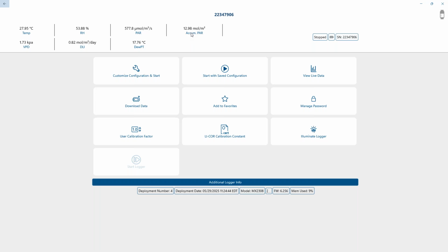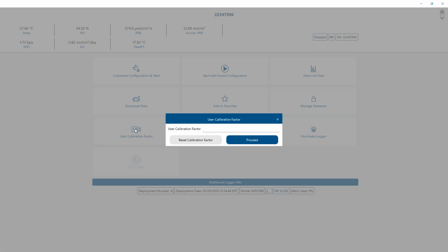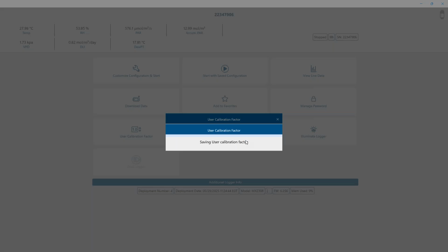I have this one logging every minute. You can see it just updated a second ago. So this will update at the logging interval. The user calibration factor that I touched on, let's imagine you 2 years down the line and you want to use this product. For the user calibration factor, this is where by default is 1.1. If you wanted to change it, you select it and it will save it. So essentially from this point on, every measurement that's made, this 1.1 will be applied to it.